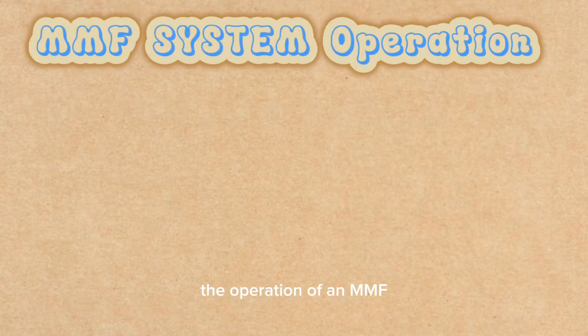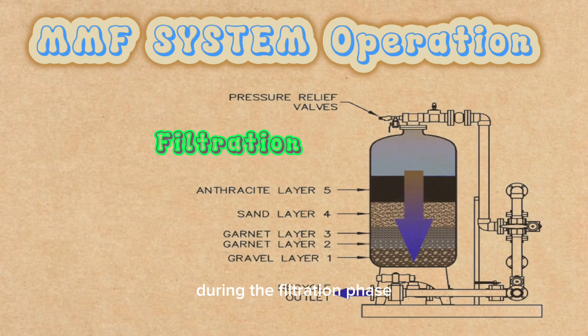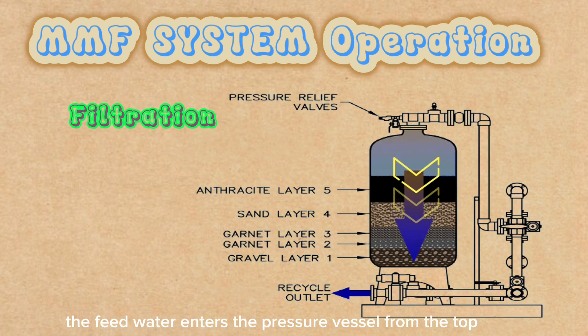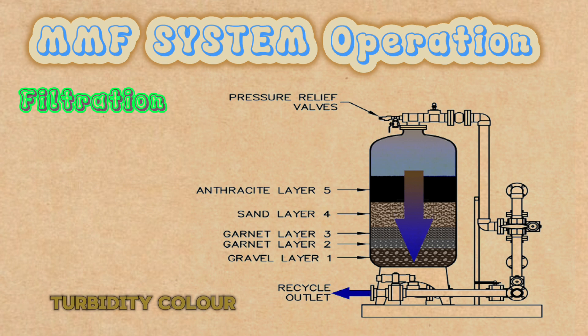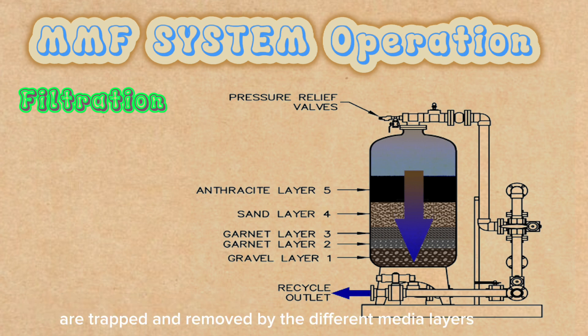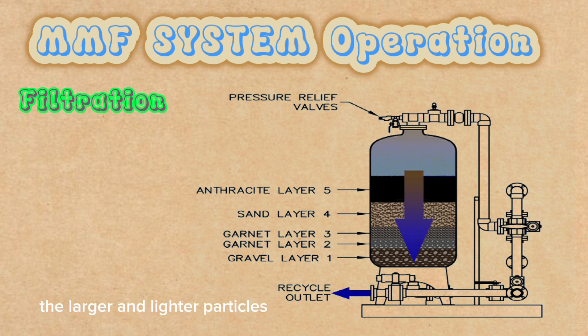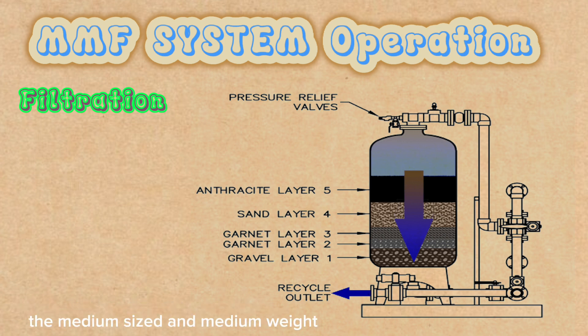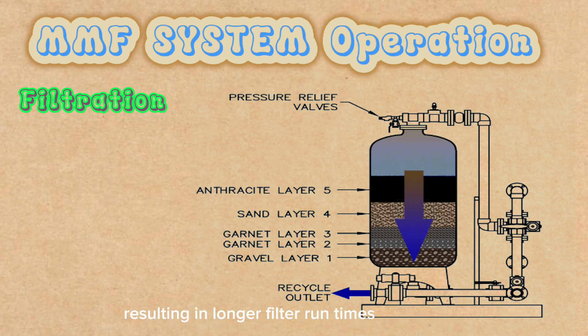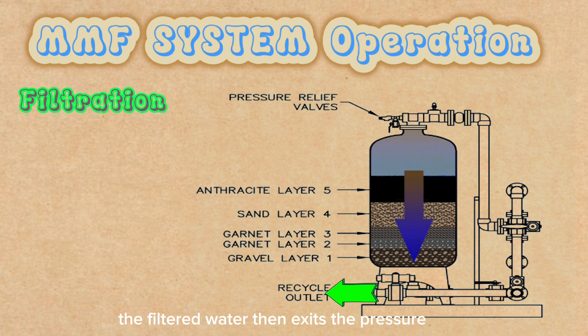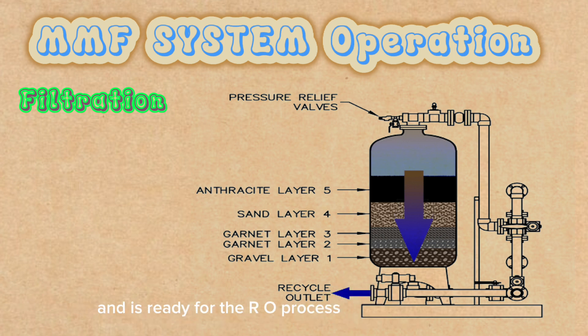The operation of an MMF system can be divided into two phases: filtration and backwash. During the filtration phase, the feed water enters the pressure vessel from the top and flows downward through the filter media. As the water passes through the filter media, the suspended solids, turbidity, color, and microorganisms are trapped and removed. The larger and lighter particles are retained by the anthracite layer, the medium-sized and medium-weight particles by the sand layer, and the smaller and heavier particles by the garnet layer. This allows the entire depth of the filter media to be used for filtration, resulting in longer filter run times and lower pressure drop. The filtered water then exits the pressure vessel from the bottom and is ready for the RO process.